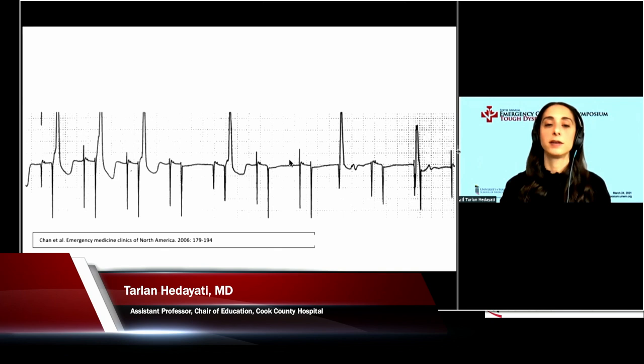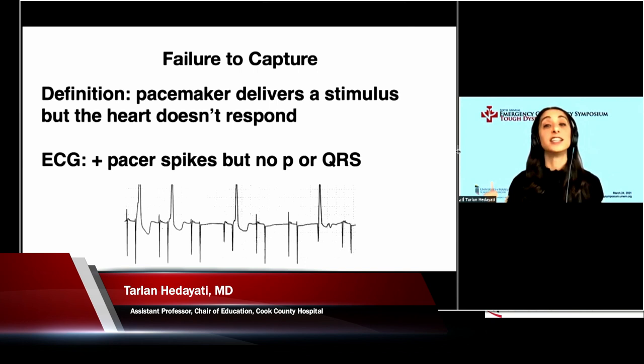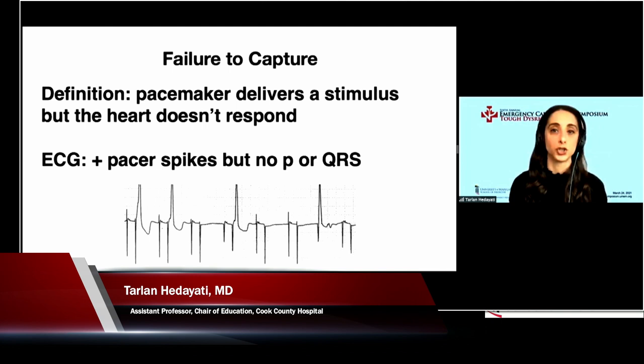This is failure to capture. This is where the pacemaker delivers the stimulus, so it's doing its job, but the heart is not responding appropriately, so it's not generating either the P wave or the QRS the way that it should. On the electrocardiogram, you're going to see pacer spikes, but you're not going to see a resultant P wave or QRS complex, depending on whether the issue is with failure to capture with the atrium or with the ventricle.